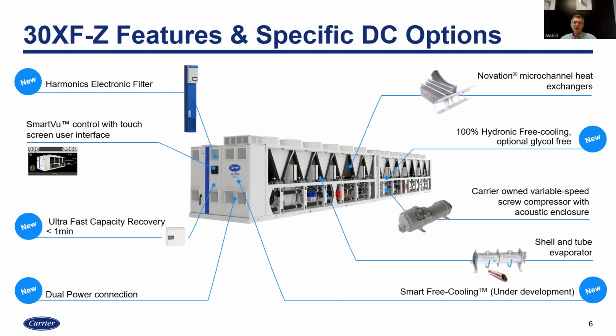Very important—I'll have a specific slide on how we arrange the evaporators, not just how we put them together but how they're designed. In data centers, customers usually like to work with a constant delta T across the evaporator—let's say entering water at 30 degrees C, leaving at 20, whatever the data center load.